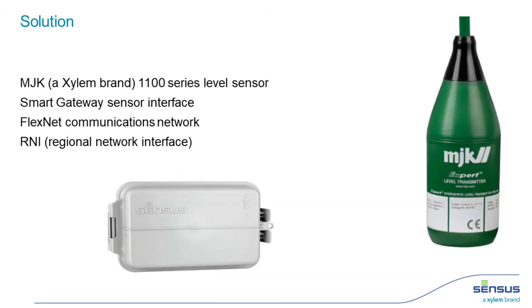The solution was pretty simple. We wanted to monitor the level, so we acquired a couple of MJK level sensors. The reason for having two sensors is we placed one upstream of the bridge and one downstream to see if there was a differential level between each side, to determine if there was a blockage or not. We paired those sensors with a smart gateway to send readings out to the regional network interface.